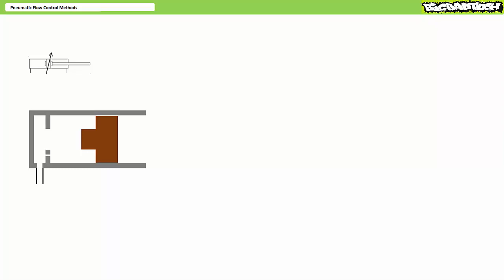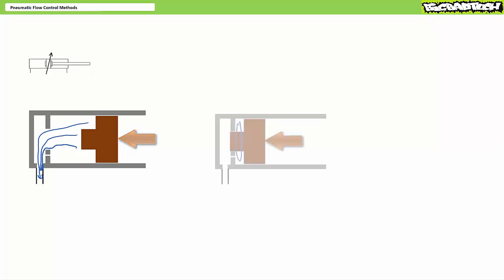Cylinders with cushions have a special shaped piston with a plug that fits into a circular depression. Here I'm illustrating a cushion on retraction in the cap end with the rod omitted for clarity. As the piston retracts mid-stroke, the plug and hole don't come into play and exhausted air has an unobstructed path out of the barrel. However, as the piston nears the limits of retraction, the plug fits into the hole blocking the larger port, leaving the cushion of air trapped between the piston and the ring with a narrow restriction as the only means for air to exhaust.